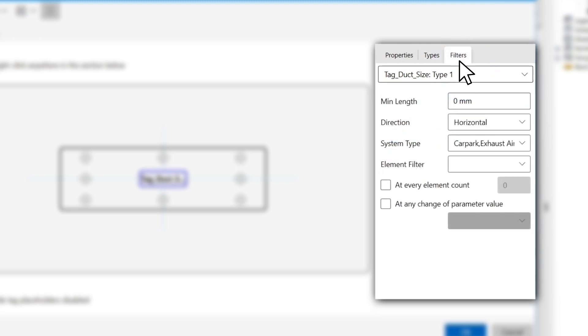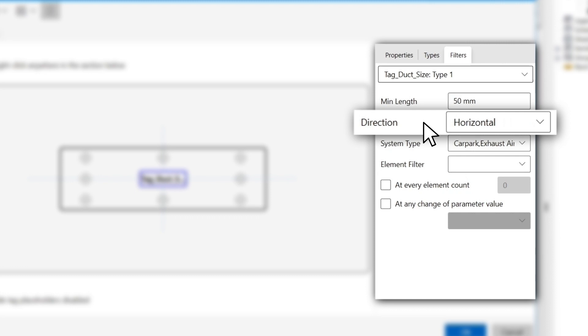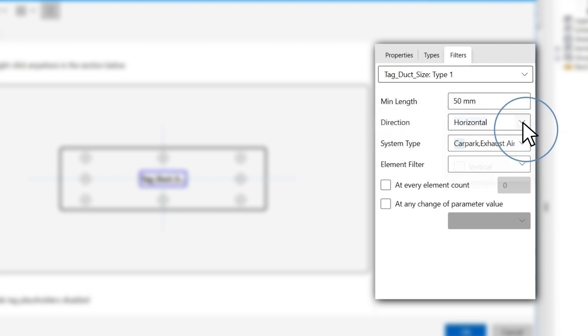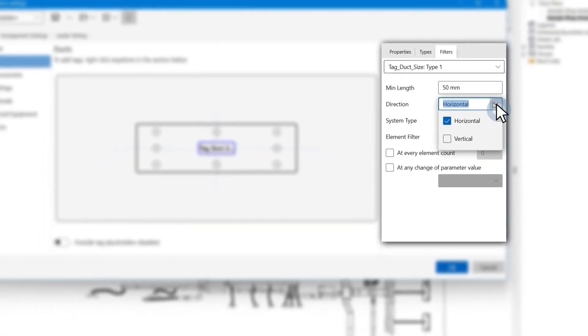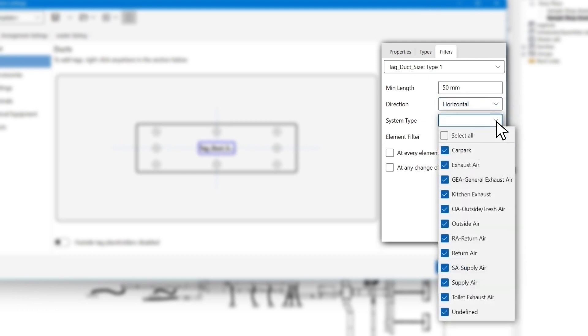Now that I have selected the family types we want to tag, we are able to fix some more parameters using the filter tab. You can filter out any of the ducts that are less than a certain length in the minimum length filter. For example, in this video we don't want to tag any duct less than 50mm in length. The direction filter is used to differentiate the riser versus normal ducts or pipes in case you wanted to have different tags dependent on the direction of the duct.